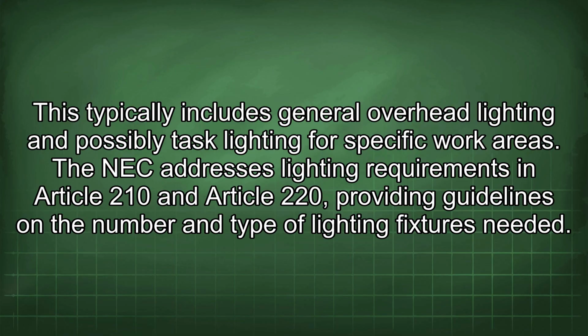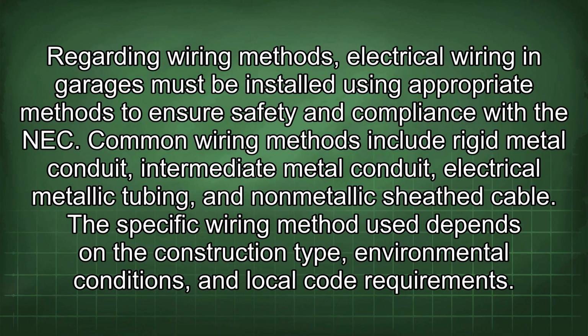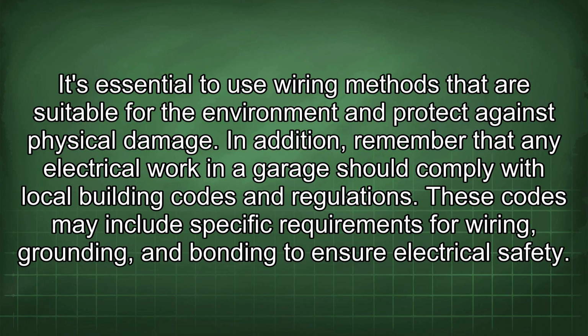Regarding wiring methods, electrical wiring in garages must be installed using appropriate methods to ensure safety and compliance with the NEC. Common wiring methods include rigid metal conduit, intermediate metal conduit, electrical metallic tubing, and non-metallic sheath cable. The specific wiring method used depends on the construction type, environmental conditions, and local code requirements. It's essential to use wiring methods that are suitable for the environment and protect against physical damage.